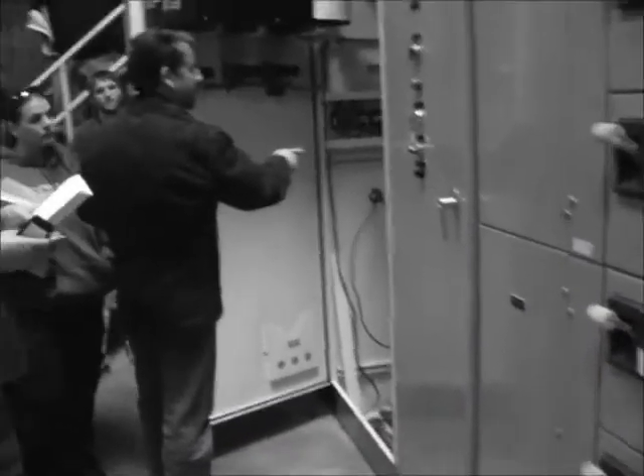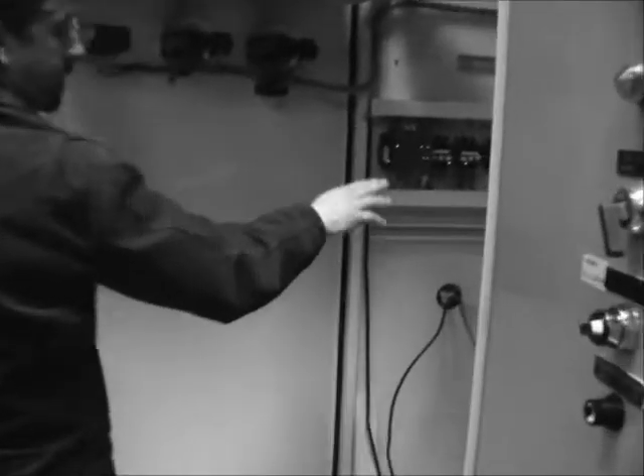The new item we put in, this PLC, is basically a glorified timer. It tells what pump to come on when. Or if a pump has failed, it'll tell the pressure switches not to call for that certain pump.